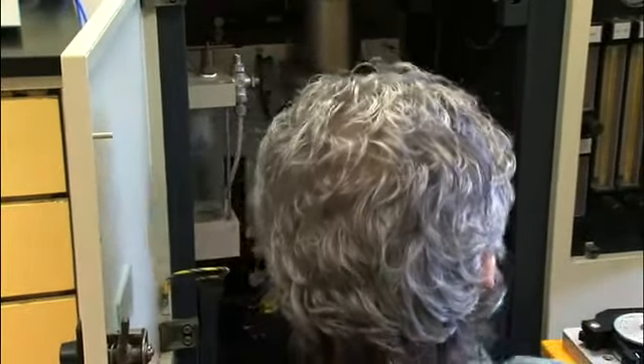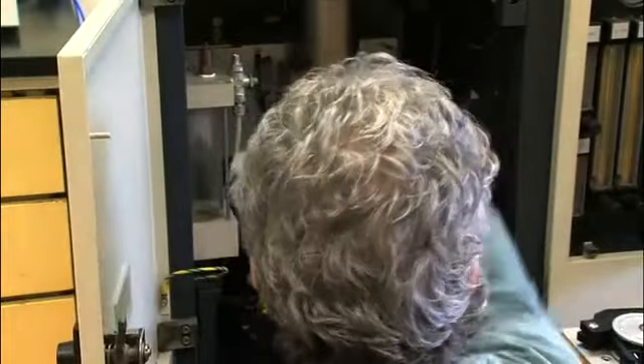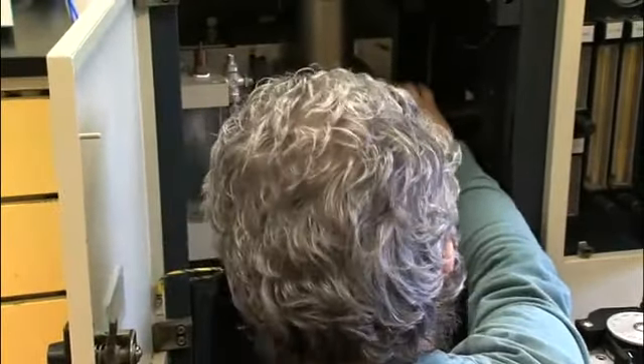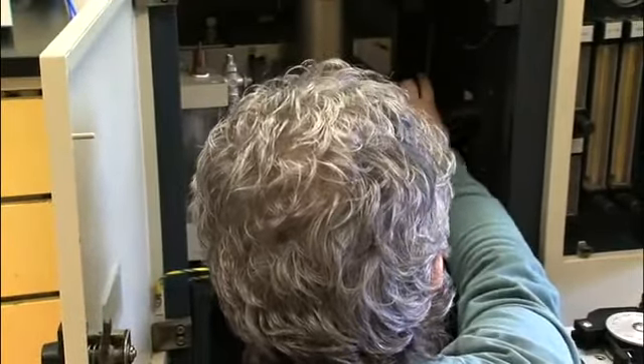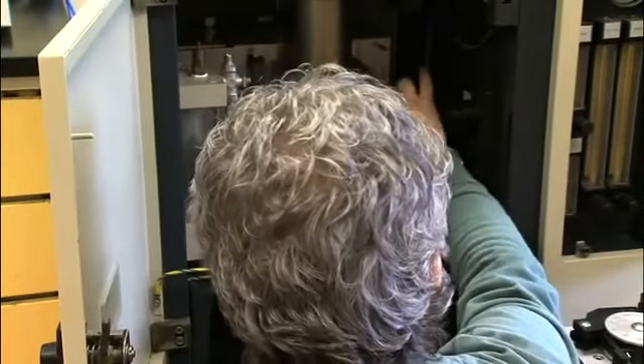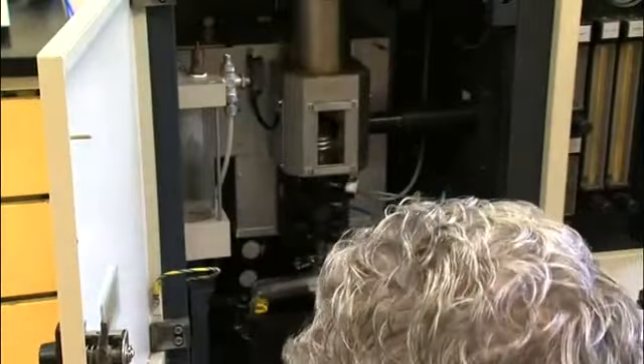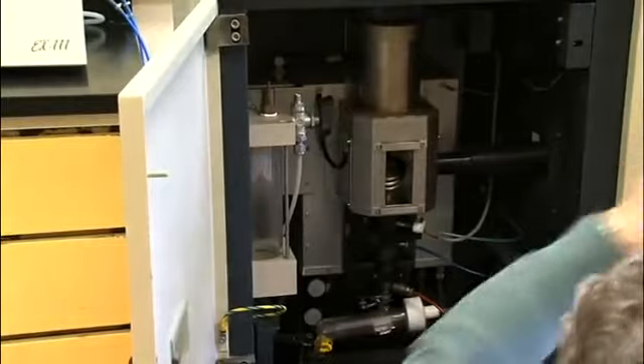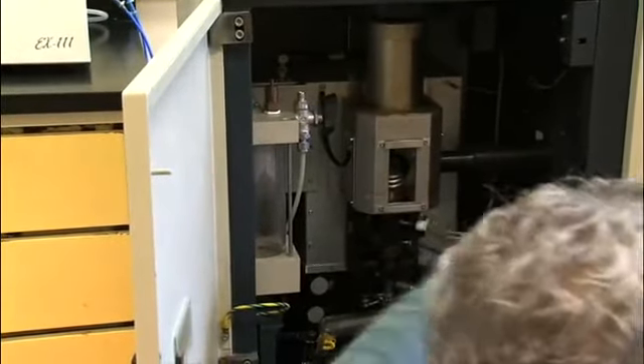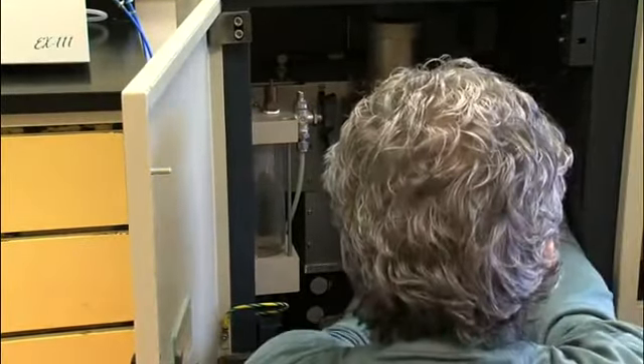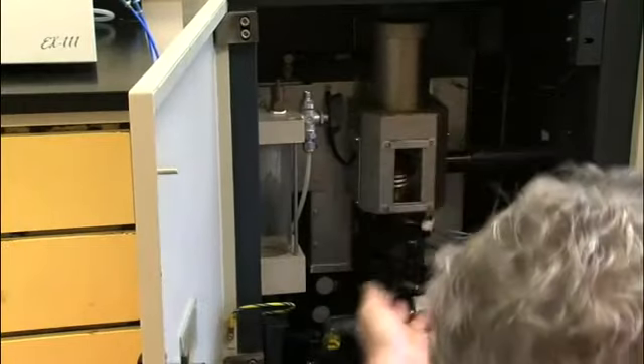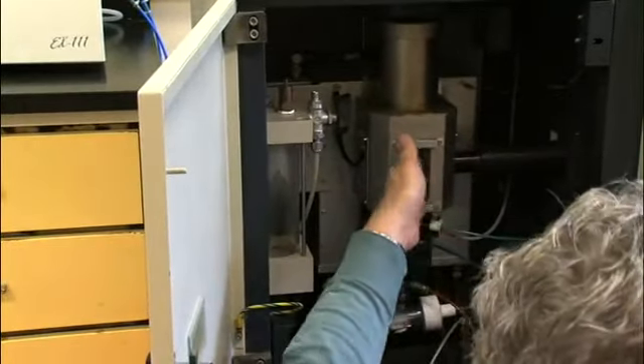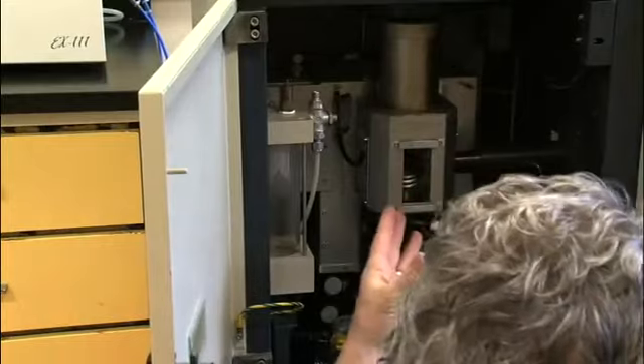If you've taken the optical channel back, you want to put it forward as close as you can get it to the plasma without it touching that or the quartz tube or the coil, because if you're looking for elements in the UV and you've purged with nitrogen, you need to have that nitrogen come and fill the entire optical path. So this has to come all the way out to the plasma. If you have air between the plasma and the optical channel, it's going to absorb those UV lines, so you're not going to see anything.